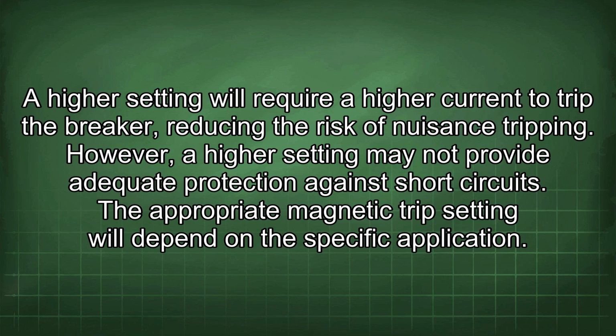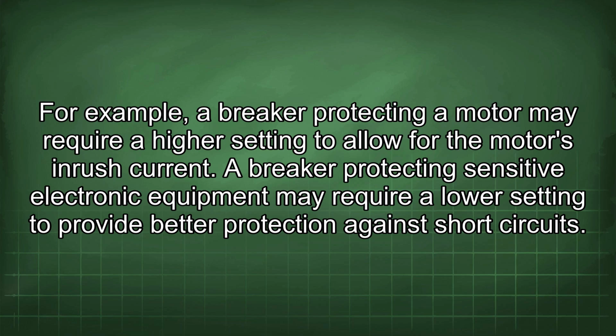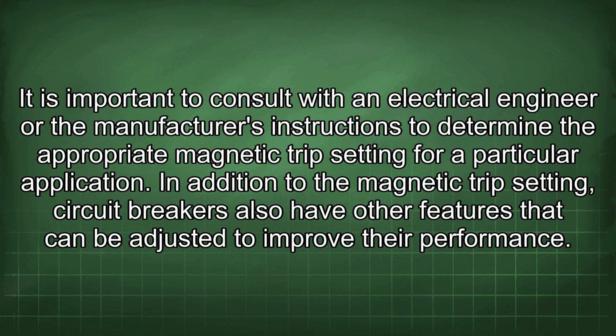The appropriate magnetic trip setting will depend on the specific application. For example, a breaker protecting a motor may require a higher setting to allow for the motor's inrush current. A breaker protecting sensitive electronic equipment may require a lower setting to provide better protection against short circuits. It is important to consult with an electrical engineer or the manufacturer's instructions to determine the appropriate magnetic trip setting for a particular application. In addition to the magnetic trip setting, circuit breakers also have other features that can be adjusted to improve their performance.